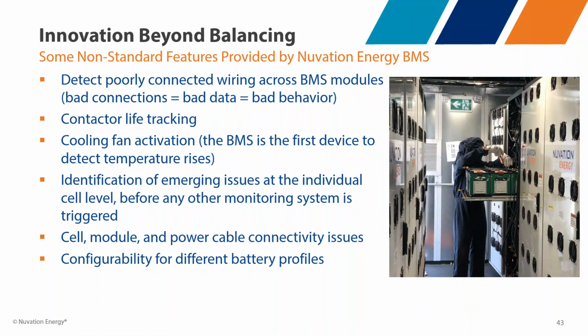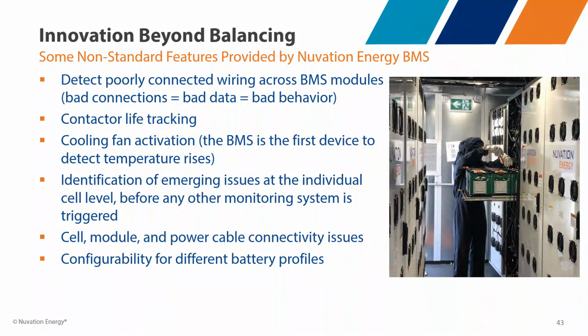We also have cooling fan activation. The BMS is the first device to detect a rise in cell temperature inside a system, so we can turn on cooling fans only when needed, rather than having fans running all the time. I've certainly been in energy storage systems where the system's idling and fans are running anyway. One advantage of a Nuvation BMS is that we control cooling fans as a function of cell temperature.